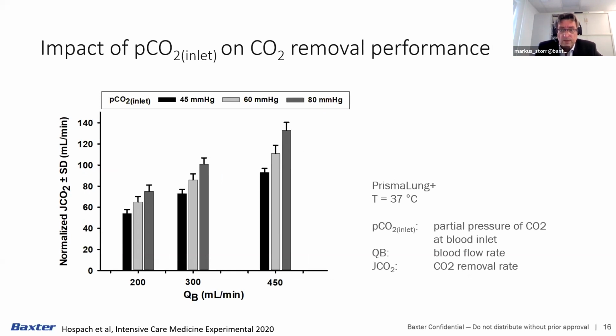Here we see the CO2 removal rates for PRISMALUNG Plus at different inlet PCO2 levels. As expected, removal rates increase with increasing PCO2. You also see that at the extreme conditions we have selected, blood flow 450 mL per minute and inlet PCO2 of 80 millimeter mercury, a CO2 removal rate of more than 130, I think 133 mL per minute, was demonstrated for the PRISMALUNG Plus device.